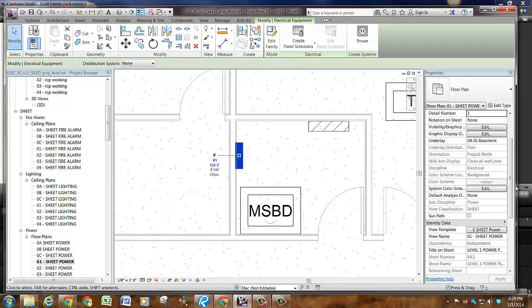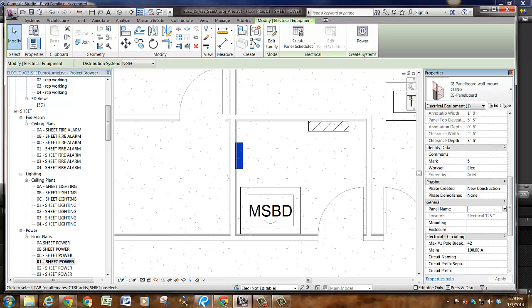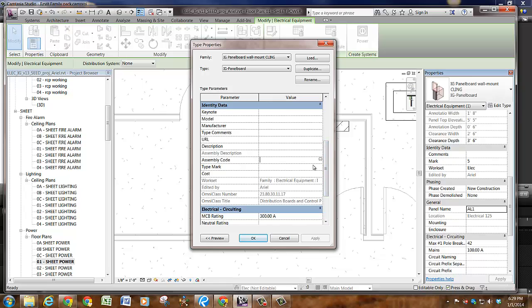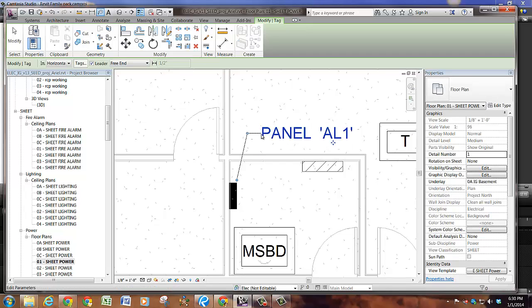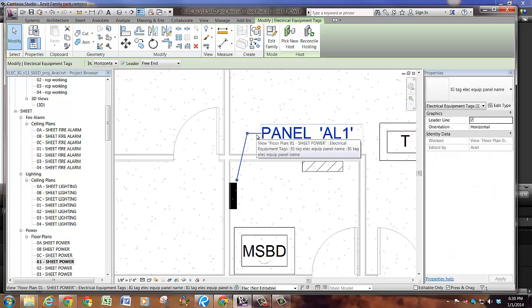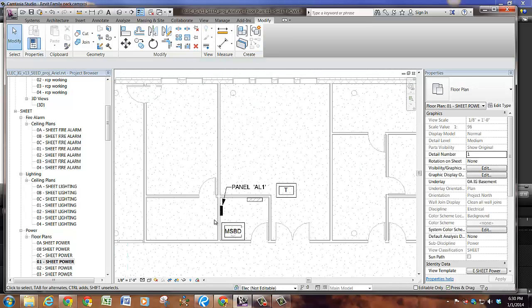When you go to name your panel, you do not need to type 'panel' in there — it will automatically add that. So let's say this panel is AL1. When you go to edit type, the type mark you want to place in here is 'panel' or 'PNL' if you prefer. This works the same as a light fixture. When you go to tag this panel, we don't want free attachment, we want free end — it will add those marks. Also, when you tag in a project with freshly loaded families, they won't have their arrow on them. It's an easy fix: go to leader, edit type in your tag — not your equipment, but your tag — and add arrow 30 degree filled. You'll need to do this for all your tags, but once you do it once, it will last for the rest of the time.